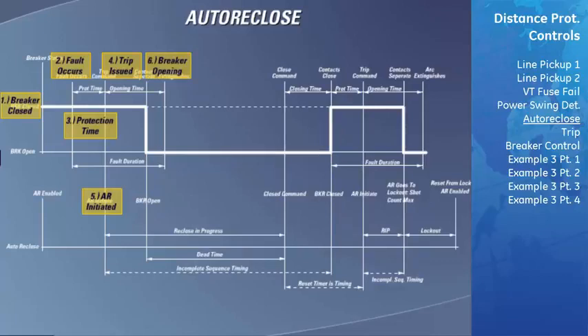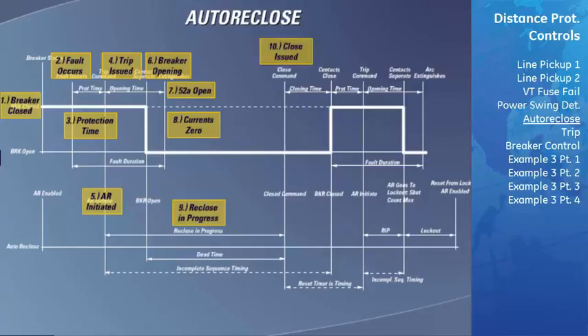At this time, the auxiliary contacts will have signaled this open status to the D60. This also starts the three-pole dead time 1 timer. The actual breaker currents will finally drop down to 0 amps. The reclose in progress state remains active until the three-pole dead time 1 timer times out. Once the three-pole dead timer 1 has expired and a reclose command is issued by the D60, the shot counter is changed from 0 to 1. There will now be a delay as the breaker takes some time to close.